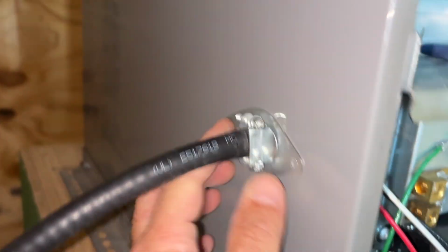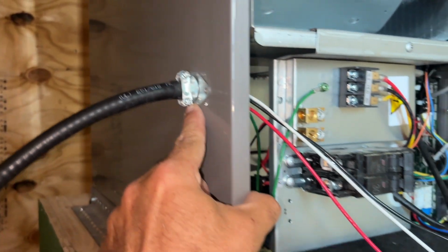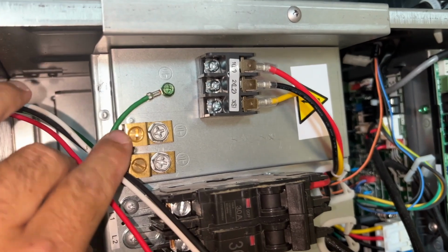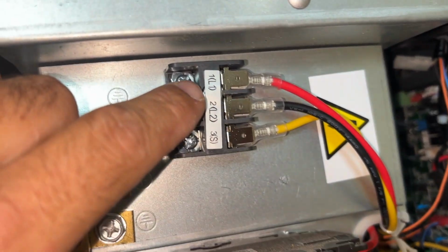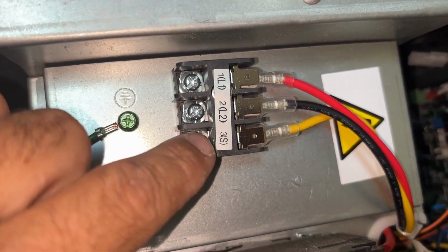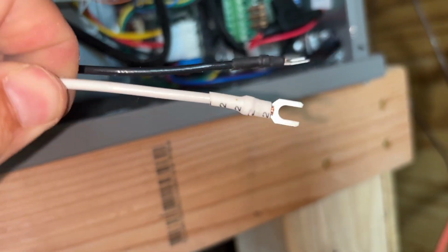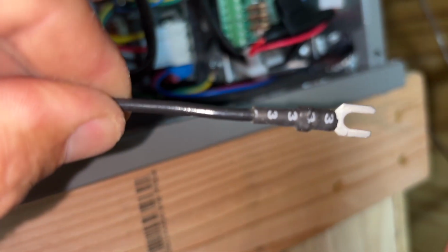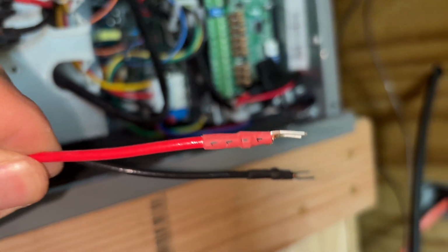All right, so this is where we're at. We're coming into the unit here with the power from the outdoor unit. We have the ground hooked up, and then you can see here 1, 2, and 3. And these cables are listed 2, 3, and 1 there. So we're gonna hook those up into this block here, and that'll be power for the air handler.